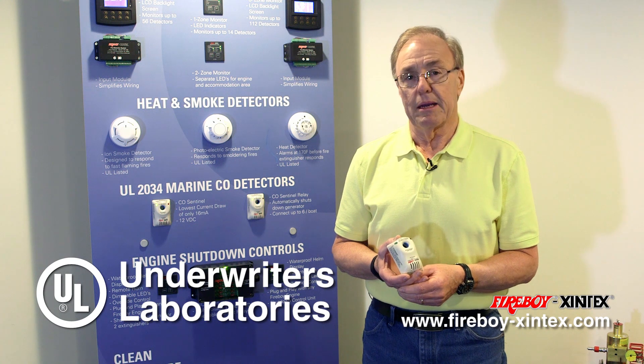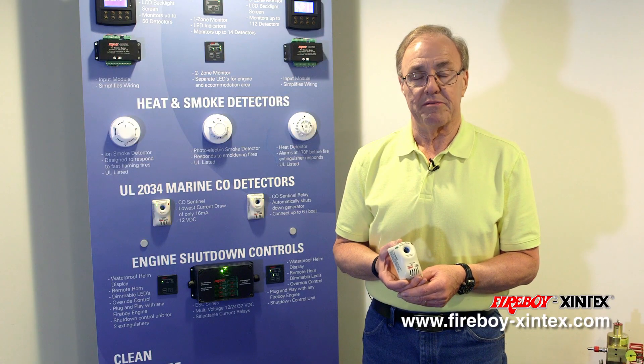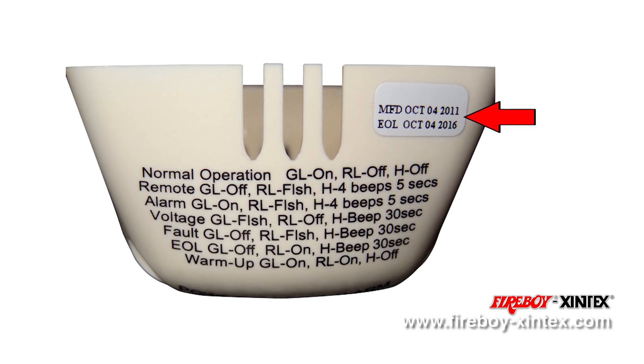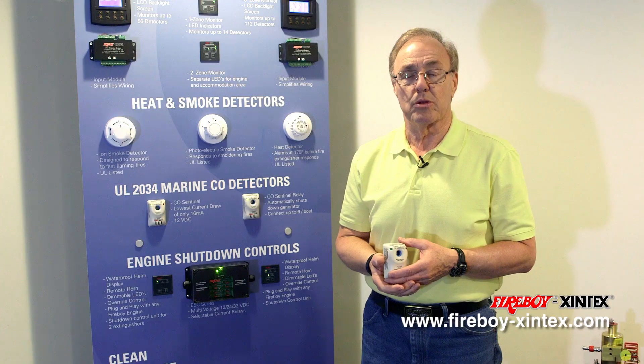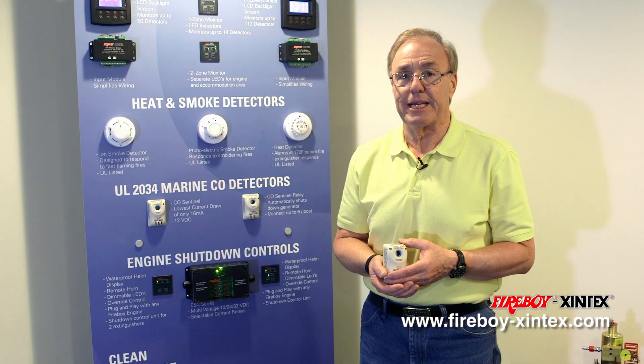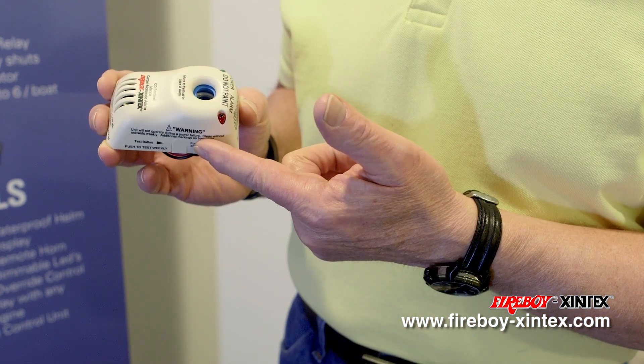UL instituted an end-of-life requirement for all carbon monoxide detectors. The Fireboy Xintex CO detectors now have a five-year end-of-life cycle. On the top cover is the label indicating the date of manufacture and the end-of-life date. At four years and eleven months, the carbon monoxide detector will enter into the beginning of the end-of-life signaling. At that point, the CO detector can be silenced for three days at a time by depressing the test reset button on the side of the unit.